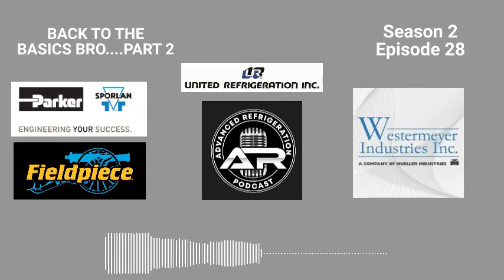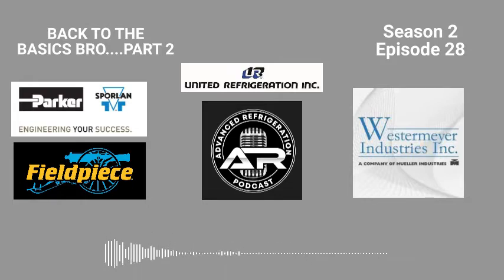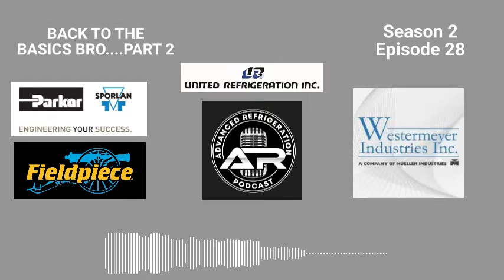Those valves are either on point, like they hold 0.2 of a degree of superheat, or they hunt all over the place or don't feed at all. Have you? So I'm talking about, if anyone doesn't know, the Danfoss. They look like they're silver.